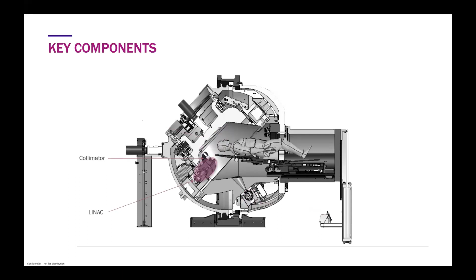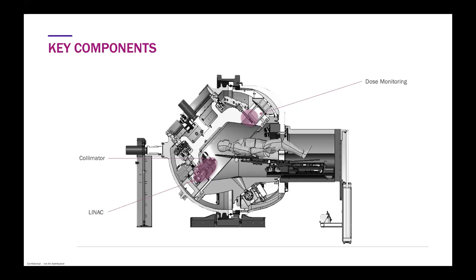And very interestingly, for the first time ever, we have a real-time dose monitoring tool of transit dosimetry. We're not just measuring dose exit from the head of the collimation system, we're measuring it transmitting through the patient's head. And from now on, in a QA process, you have real-time confirmation of the dose you're delivering. You're no longer basing your assumptions all on machine calibration. So if someone makes a mistake in the calibration process, we'll know and we'll be able to check it before anything bad happens to a patient. And those of us who've been around radiosurgery for a while know that some of the most horrific injuries in all of radiation therapy have been in the world of radiosurgery because machines were miscalibrated.